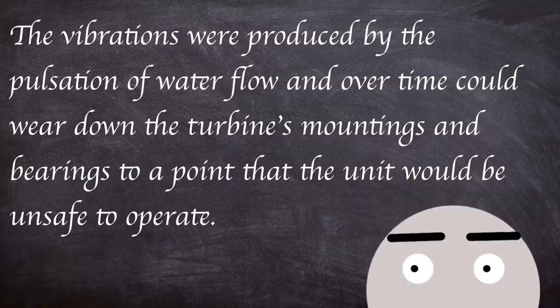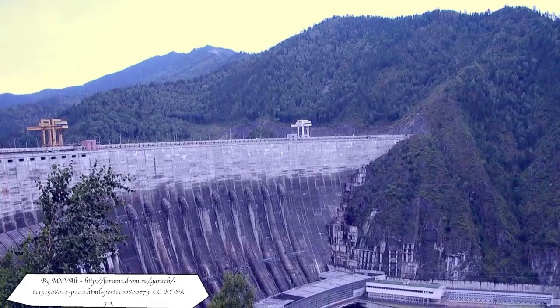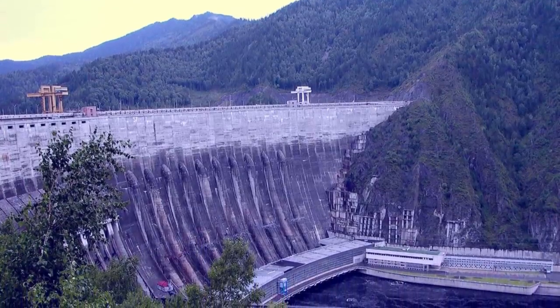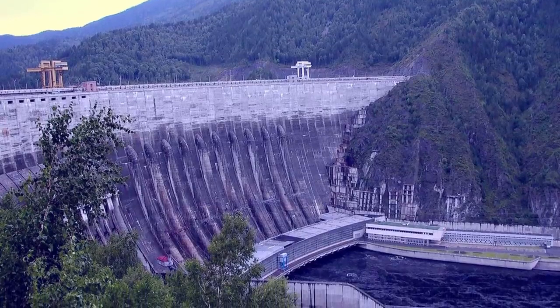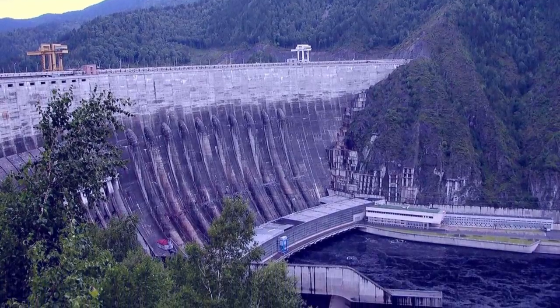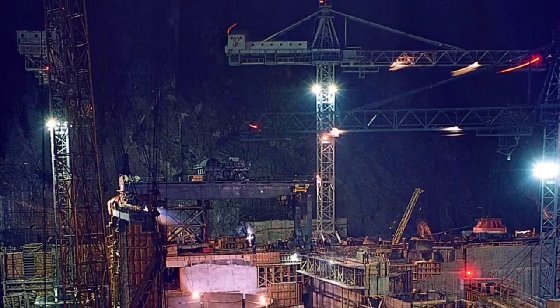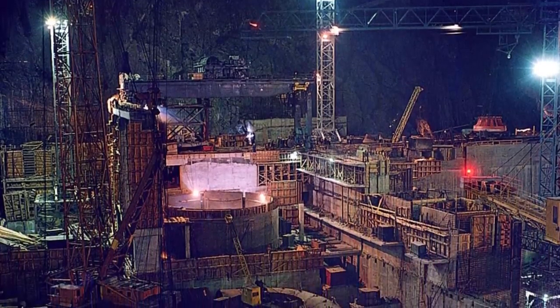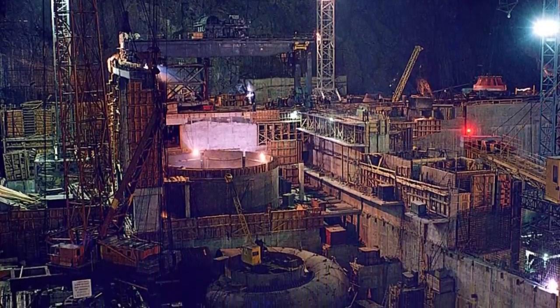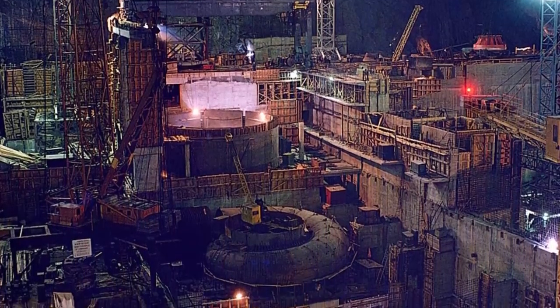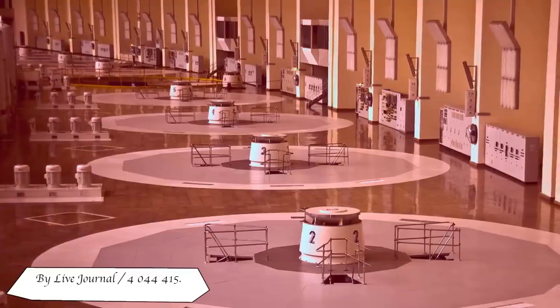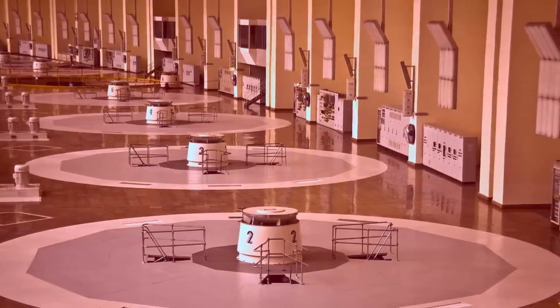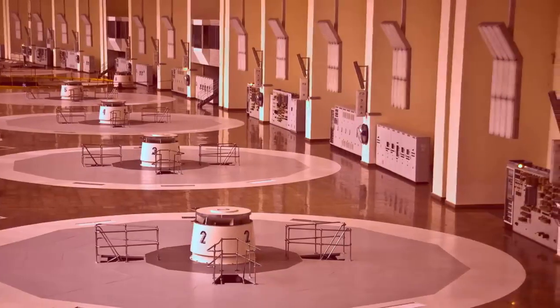The vibrations were produced by the pulsation of the water flow and over time could wear down the turbine's mountings and bearings to a point that the unit would be unsafe to operate. The hydroelectric plant's lifetime has been mired with various issues. Many of the turbines experienced seal, vibration, and bearing issues, as well as several floods. Turbine 2 had its fair share of issues ever since its installation in 1979. This particular unit had seemed to have taken a lot of the brunt of the extreme forces put upon it during its operating life. As such, by the early 2000s it was showing its age with cracks in the turbine runner, and issues with bearings were also highlighted and replaced.